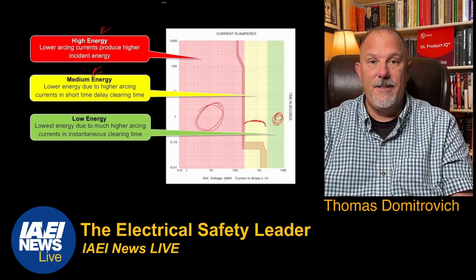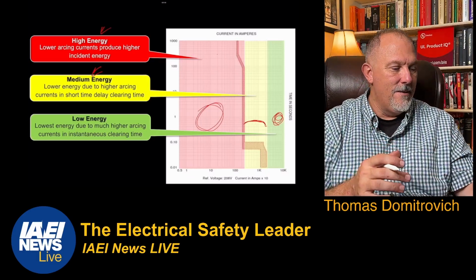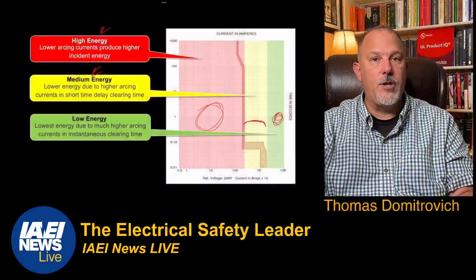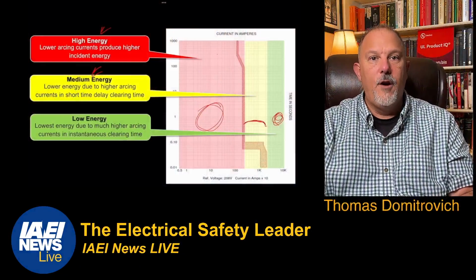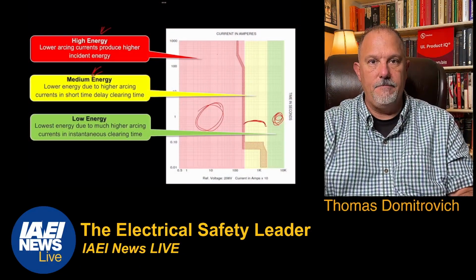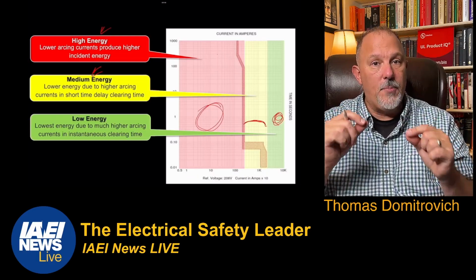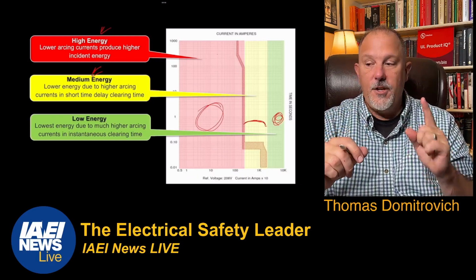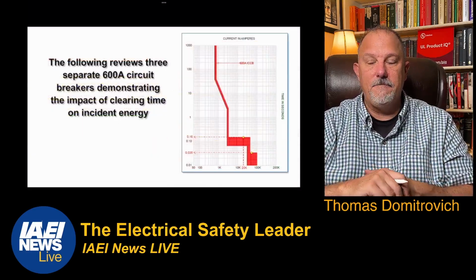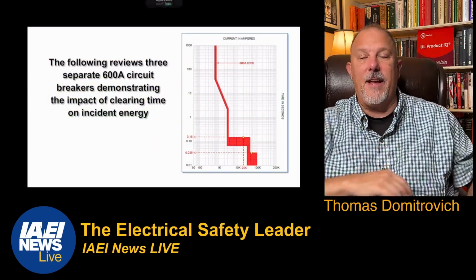So, this is what a lot of people don't understand. Higher fault currents will give me lower values of incident energy because higher fault currents produce higher arcing currents, which put you into the zone of protection for a very fast clearing time. That is a critical piece of the pie. You've got to understand that aspect. Now, this is the 600 amp. Remember I said earlier.